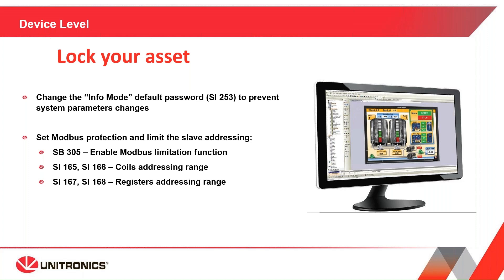The second topic is enabling Modbus limitation. If you look at the Vision help section, you will find that the Vision and Samba PLC slave addressing is entirely exposed — once Modbus is enabled, everyone can access every bit, memory integer, memory long, system double word, and so on. Usually we don't want master devices to freely write over our range of internal registers. The Modbus limitation functionality, enabled using system bit 305, addresses this. System integers 165 and 166 define the start and end addressing of the coils, and 167 and 168 define the start and end addressing of the registers.